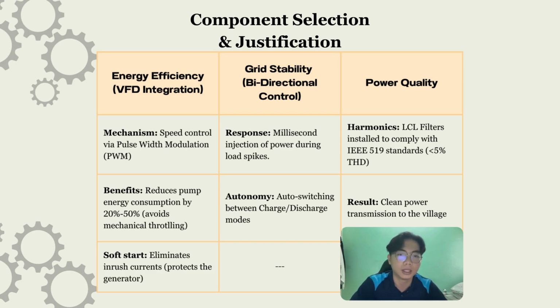Next is the stability. The two-way battery converter I mentioned, the bidirectional converter, acts like a shock absorber. If a big machine starts up and spikes the load, the battery instantly injects power to keep the voltage steady. So there will be no flickering lights when a big machine is switched on.